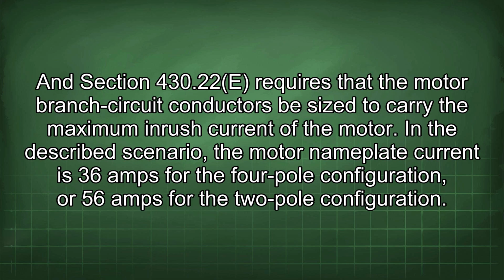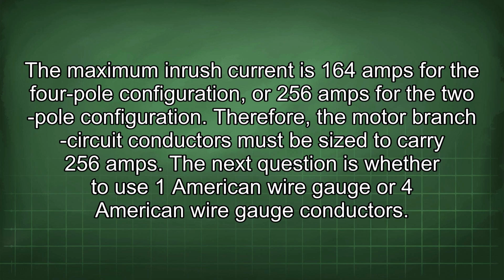In the described scenario, the motor nameplate current is 36 amps for the 4-pole configuration or 56 amps for the 2-pole configuration. The maximum inrush current is 164 amps for the 4-pole configuration or 256 amps for the 2-pole configuration. Therefore, the motor branch circuit conductors must be sized to carry 256 amps.